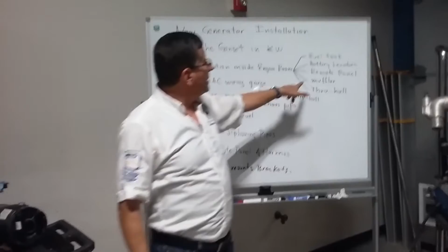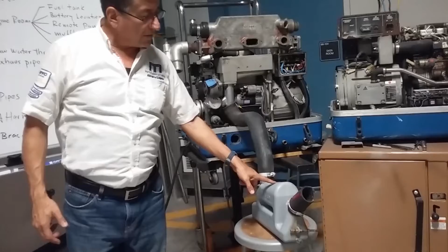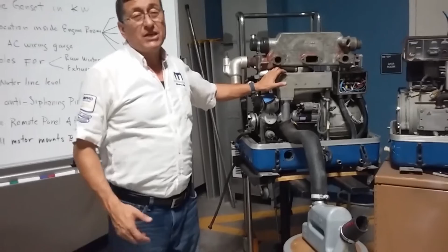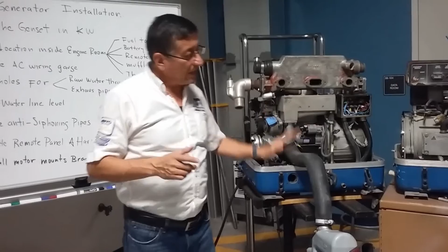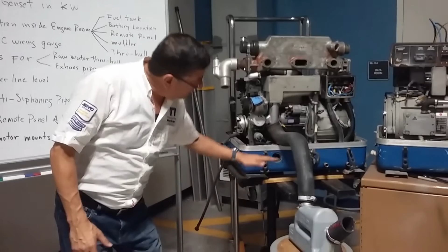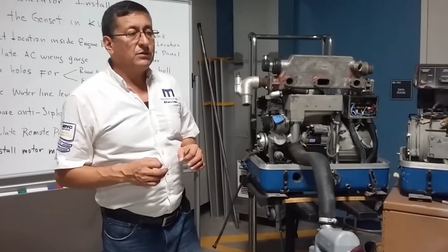The muffler is an important element, because depending on its position, the generator is considered properly installed or not. Be careful with the installation of the muffler. It should be located below the level of the generator, minimum 2 inches. This is an important recommendation.